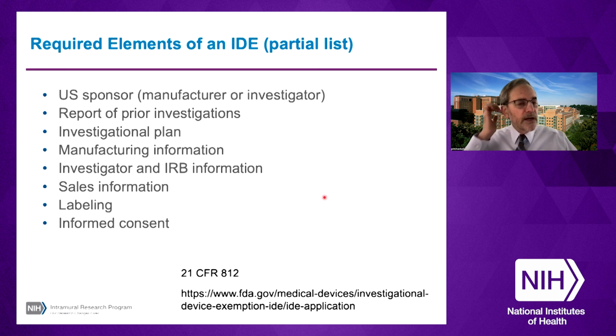So if you have to submit an IDE to the FDA, there's a number of requirements. The highlights are there has to be a U.S. sponsor. The report of prior investigations is critical. In this section of the application, you present the knowledge base of what's known about the device, but it's essential that you include any information about adverse safety events that may have happened. You include your investigational plan, manufacturing information, and so on.